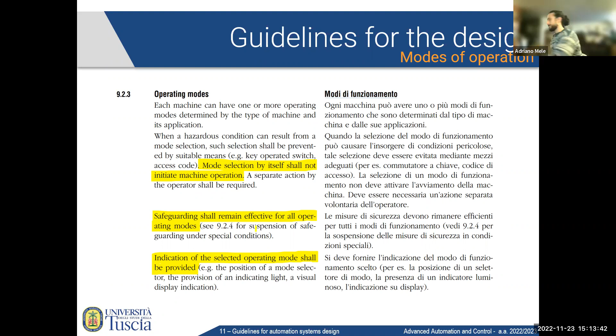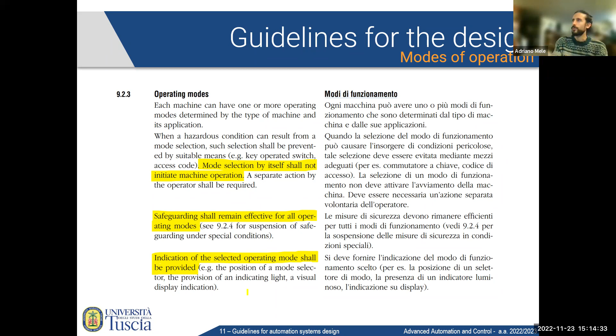An indication of the selected operating mode should be provided. This means that from outside the plant, it should be clearly visible which mode the machine is operating in. For example, with a manual and automatic mode, you could have a physical switch that tells you where you are, or a light, or a visual display indication. Anyway, you should have something that tells whoever is operating the machine what mode it's in, because you don't want to have to enter the PLC program every time you need to know what a machine is doing. You will always want to be able to tell from outside what your plant is doing. That's mostly for safety and for inspectability.